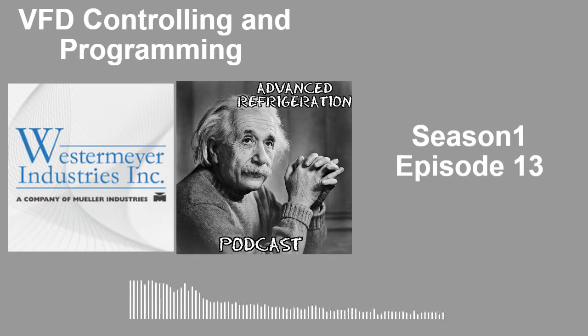Yeah, that's a whole other ball game. But with CPC, for example, Emerson, there is no max float unless you make some kind of program. It'll just keep going to the moon, till it hits that fast recovery set point and forces everything on to 100%. It'll just keep raising that SCT target to whatever the TD is plus ambient. That's the only downfall with doing TD with CPC. With Danfoss, you can actually program a min and max set point. So that's where the little issue comes in with CPC. You've got to kind of fake out the outdoor air temp sensor to make it work properly.